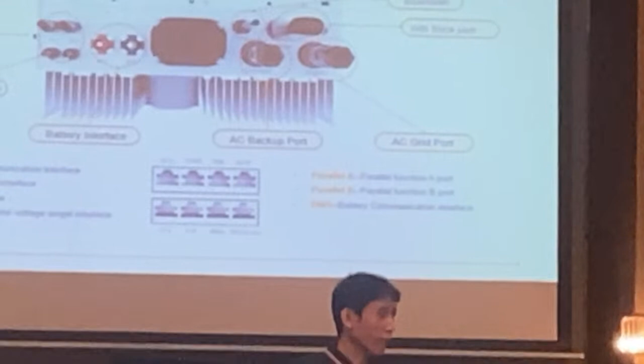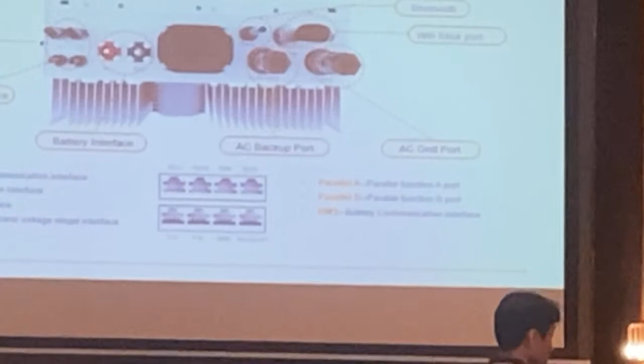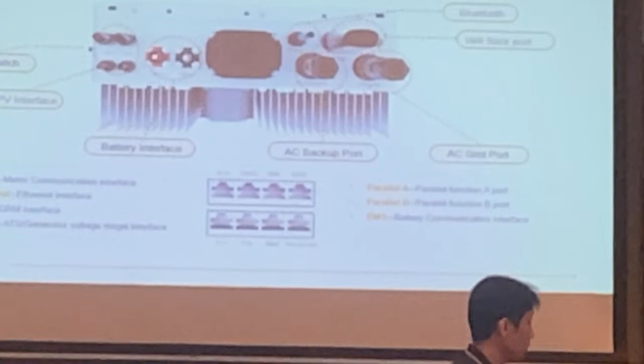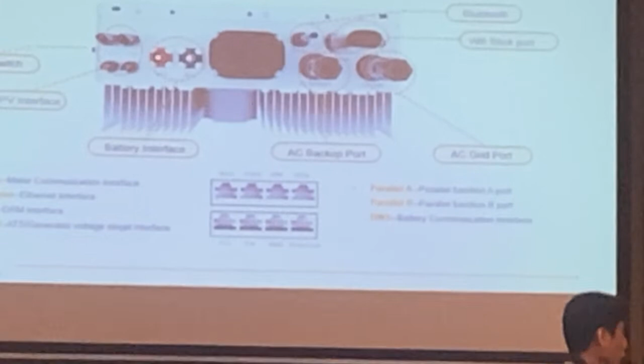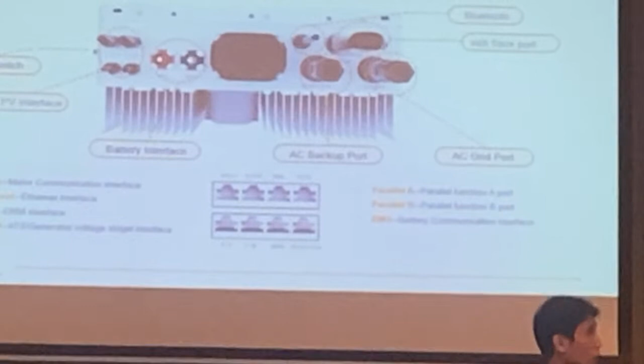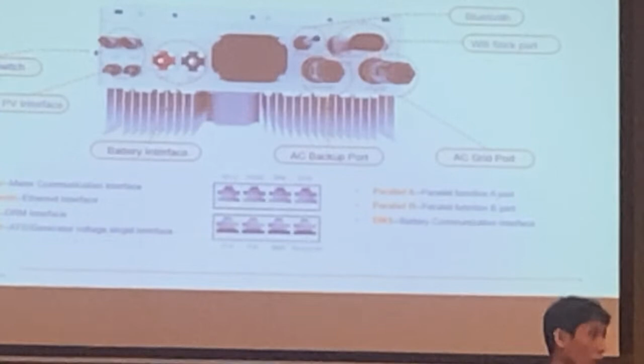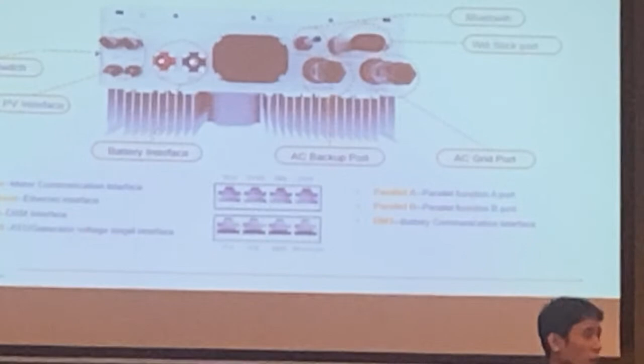The generator we test should be one available here - not industrial type, it should be commercial type generator, since this setup is only for residential use. You won't buy an industrial generator, you'd only buy something like a 6 kVA or 10 kVA generator, which doesn't have communication with the inverters. So even though we can make it work, you have to adjust the frequency mechanically. Like any Solis inverter, it has frequency settings which are variable - it has a range, lower and higher frequency up to 63. You can lower it down to 52 if you want, but beyond that it's not capable.